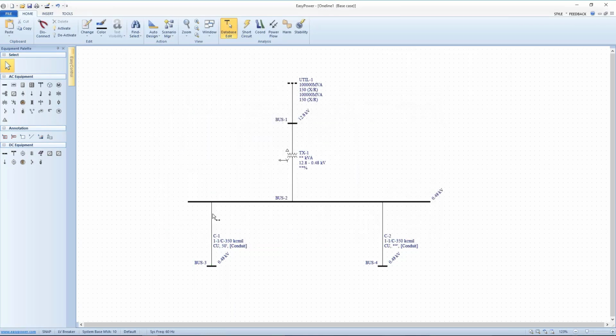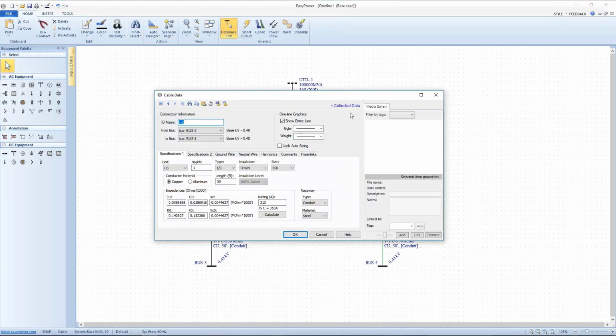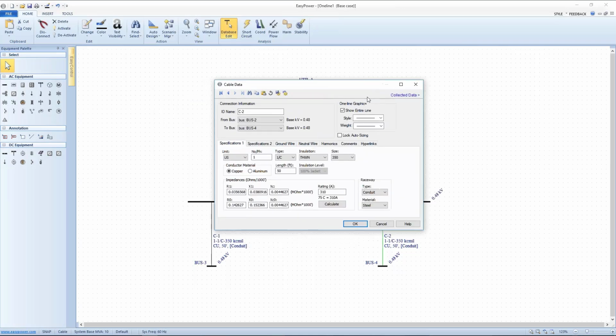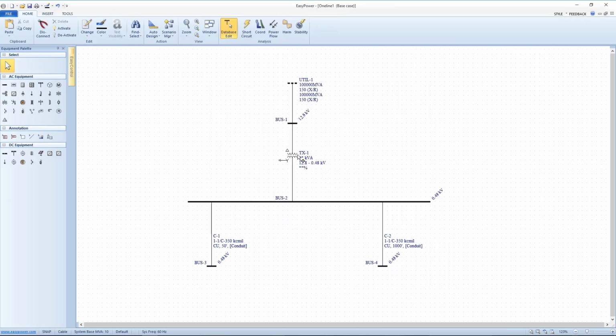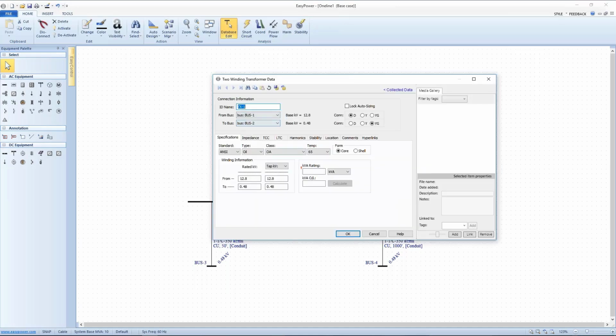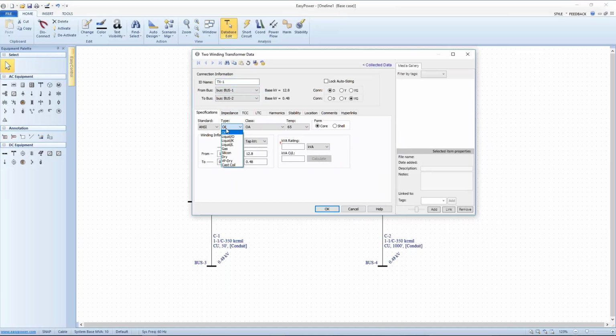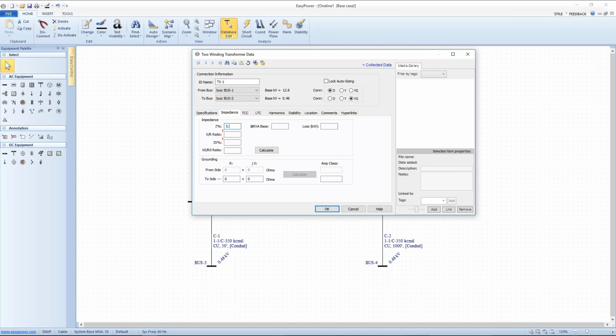So now once we've accepted those values, I can right-click and copy, and then right-click and paste, and it takes all that information over to the second cable. I'm going to double-click on it to open up the dialog box. He said the second cable is exactly the same, except it's 1,000 feet long. Now we're going to go up to the transformer and double-click on it. He said, I've looked at the nameplate on the transformer. It's an oil-filled class OA, works with a fixed 65-degree rise. It's a 1,000 kVA. The impedance on the nameplate, the impedance ratio, is 5.75%. May not have the X over R or zero sequence ratio, so we're going to calculate that.